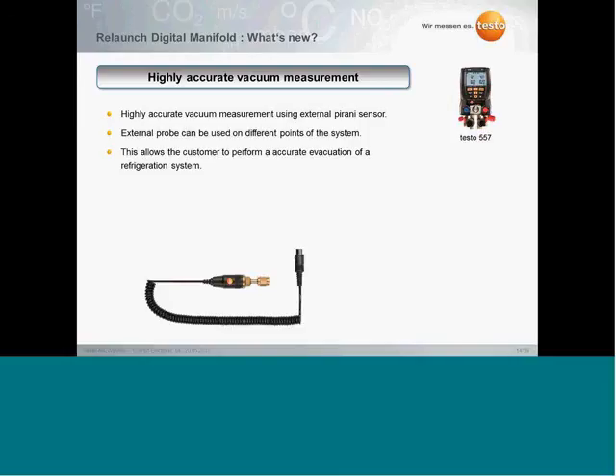The new product range includes a hybrid vacuum probe, an external probe based on a Pirani sensor. The external probe has the advantage that it can be used on different points on the system, depending on which connections a system offers you. You can connect it at different points, and of course accurate determination of the pressure is important for a good evacuation of your refrigeration system.